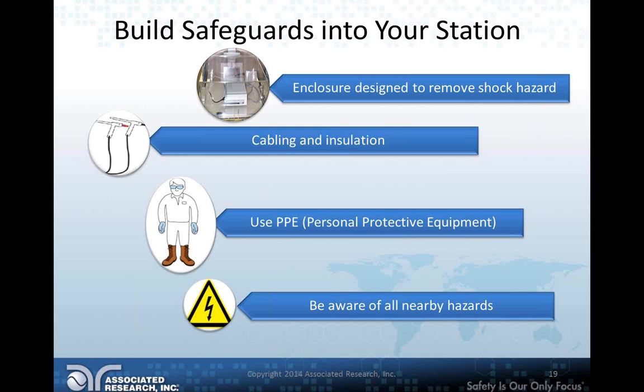There are enclosures designed to remove a shock hazard. This is actually one of the easiest ways to do this, if possible for you. Simply building an enclosure ensures that nobody can touch the product or device under test, or DUT, while it's being tested, because that door has to stay closed. I'll show some examples of this in a little bit.